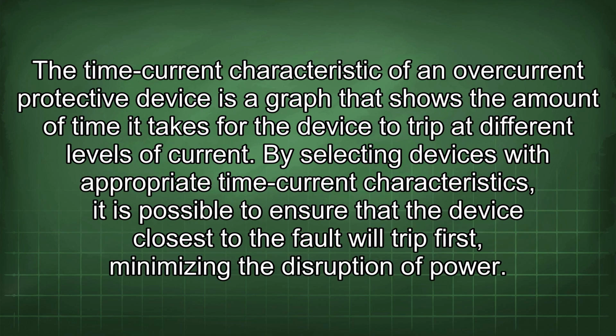The time current characteristic of an overcurrent protective device is a graph that shows the amount of time it takes for the device to trip at different levels of current. By selecting devices with appropriate time current characteristics, it is possible to ensure that the device closest to the fault will trip first, minimizing the disruption of power.